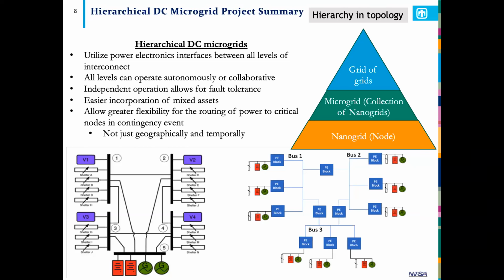At the second layer, you have a connection of nanogrids inside a microgrid, tied together by a common bus. At the third layer, you have an interconnection of microgrids to make a grid of microgrids. The key is that since each node can operate independently, it allows for greater autonomy and flexibility than would be possible with a traditional microgrid.